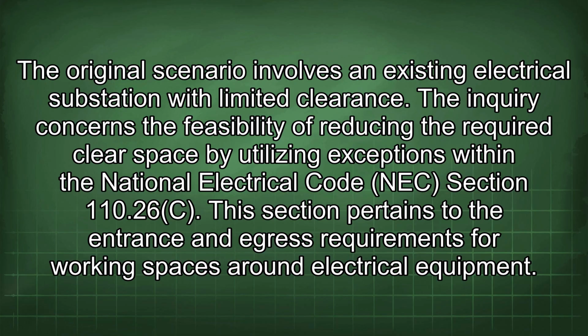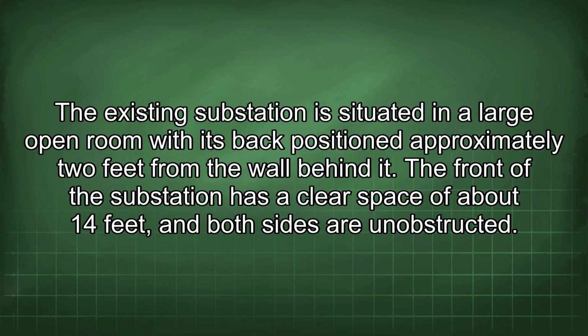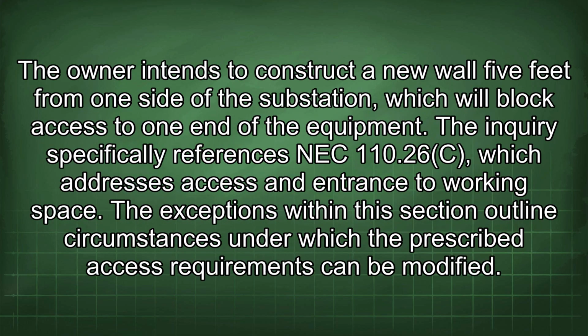The original scenario involves an existing electrical substation with limited clearance. The inquiry concerns the feasibility of reducing the required clear space by utilizing exceptions within the National Electrical Code, NEC section 110.26(C). This section pertains to the entrance and egress requirements for working spaces around electrical equipment. The existing substation is situated in a large open room with its back positioned approximately 2 feet from the wall behind it. The front of the substation has a clear space of about 14 feet, and both sides are unobstructed. The owner intends to construct a new wall 5 feet from one side of the substation, which will block access to one end of the equipment.